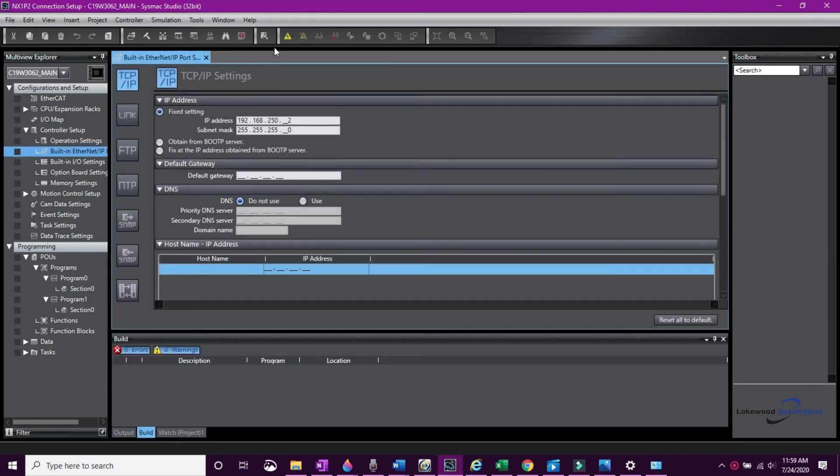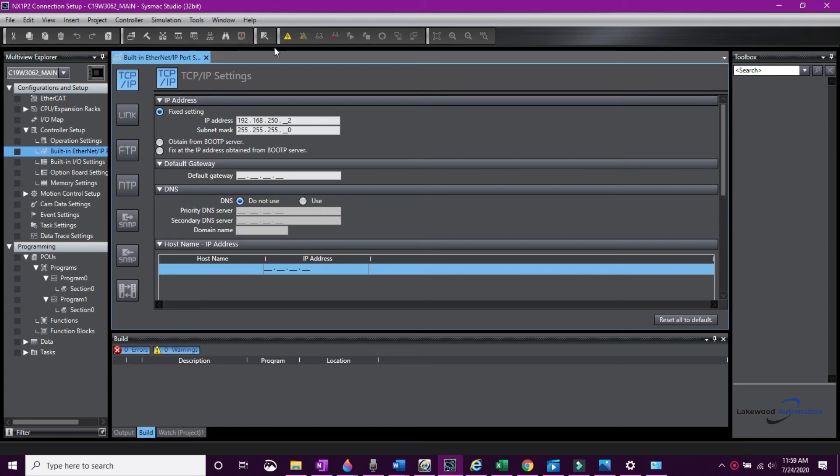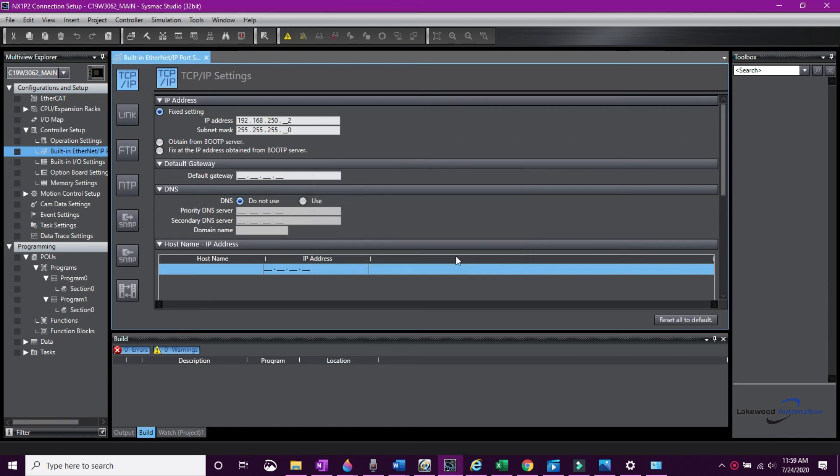Now we are going to go offline and change the default IP to whatever you want it to be for your project. In the Multiview Explorer, under Configuration and Setup, open the built-in Ethernet IP port settings. Change the IP address from default. Be sure it still matches your computer subnet.